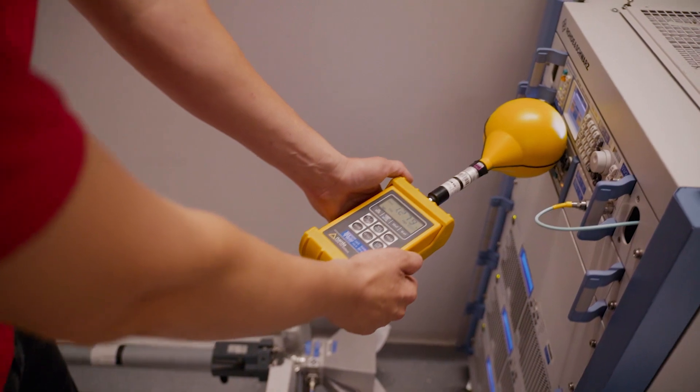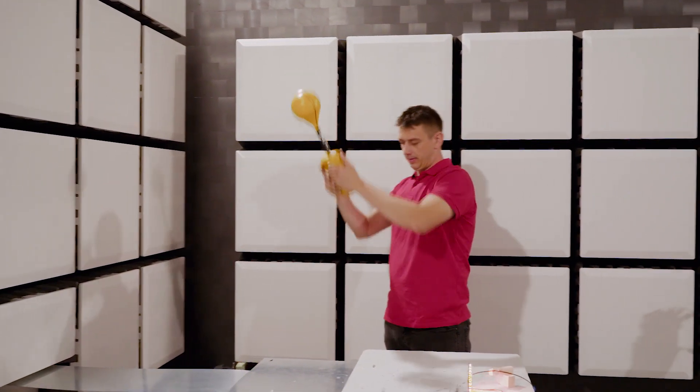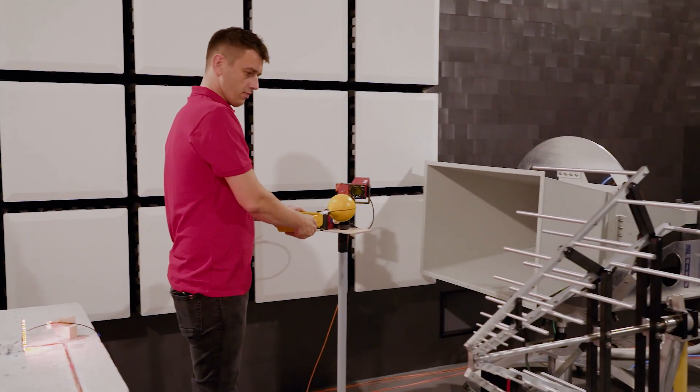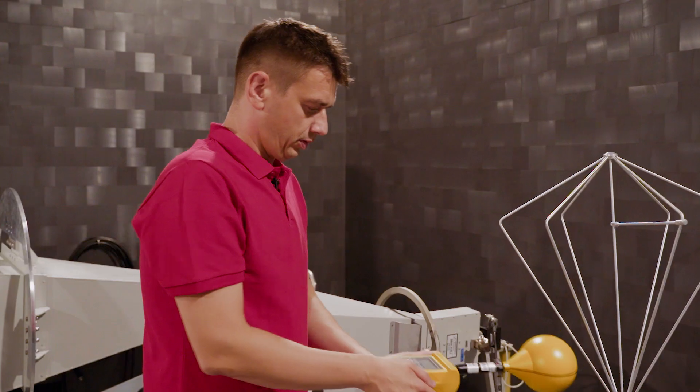How do we know when something is EMC compatible? If you see an SIQ logo on medical equipment, do not worry. Super special tests like voltage dips, proximity fields and ESD have been conducted, so the dentist can make your smile more confident. What does the EMC testing look like? First, you need a state-of-the-art and also very expensive lab, as well as highly qualified engineers. The initial step in EMC testing is placing the device into an EMC chamber and applying an electromagnetic field while observing the device. If the device is too sensitive to the electromagnetic field, it is not yet ready for the market.